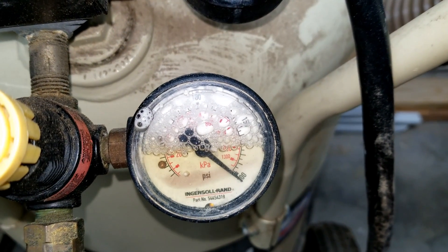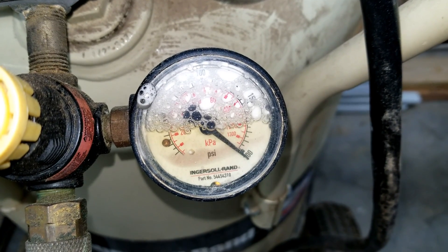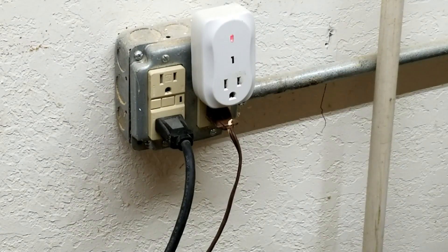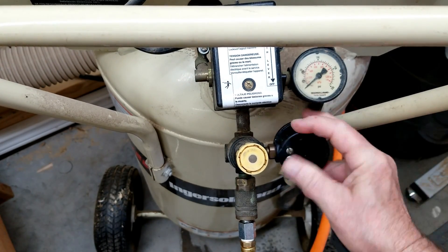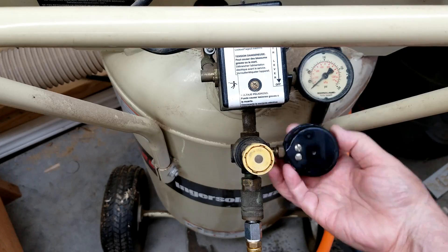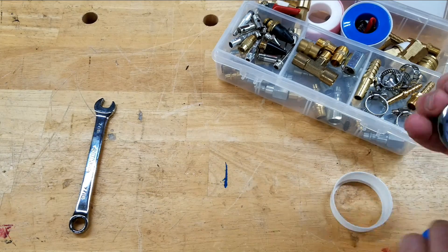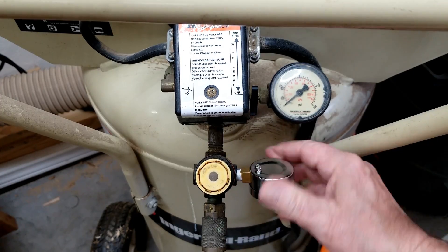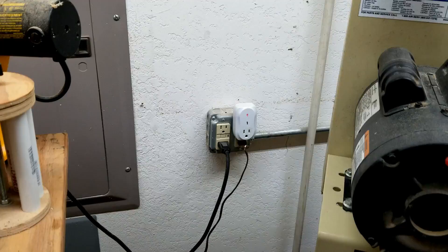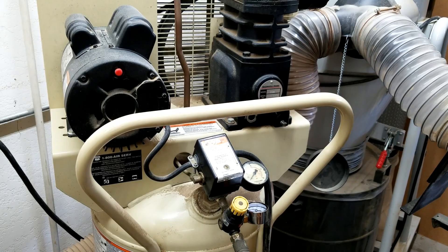When I aired it up, I discovered that one of the liquid-filled gauges had a leak and needed to be replaced. Somebody told me years ago that when you're using brass fittings, you don't need pipe dope or Teflon tape — this is not true. Don't believe it. Besides, what's it costing you to use it? Liquid-filled gauges are supposedly better than dry gauges, but the identical replacement for this gauge cost $65, so I went with a $10 dry gauge instead.